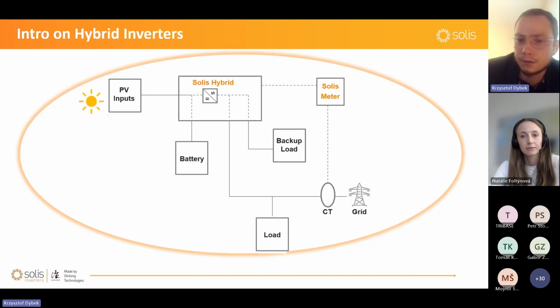It is extremely important to install meter exactly where it should be, which means before everything, before the loads, before the inverter, so it can correctly measure import, export, and react when there is grid loss on site to cut off normal circuit and let battery discharge to cover primary load, backup load, in other words, or just cover normal load when needed and grid power is working as it should be.